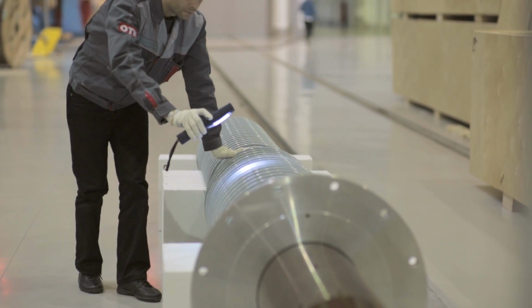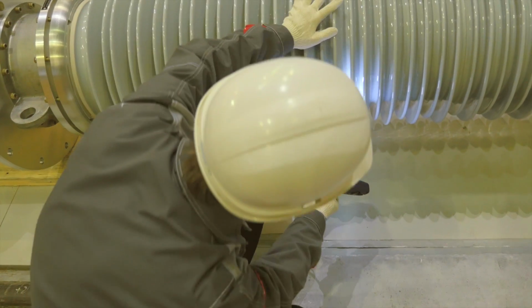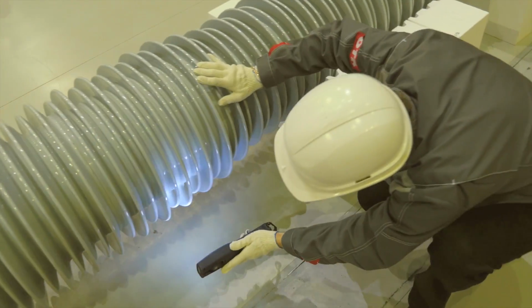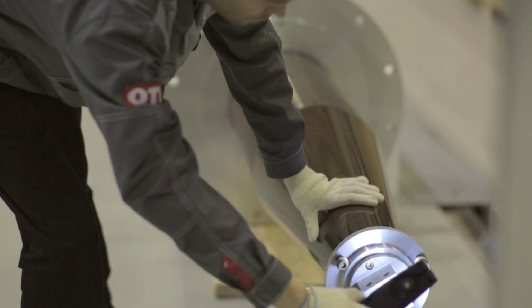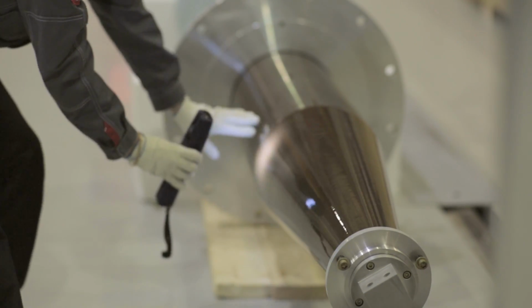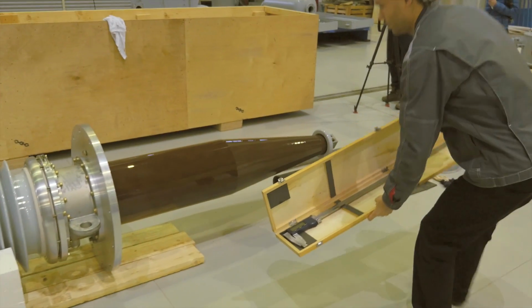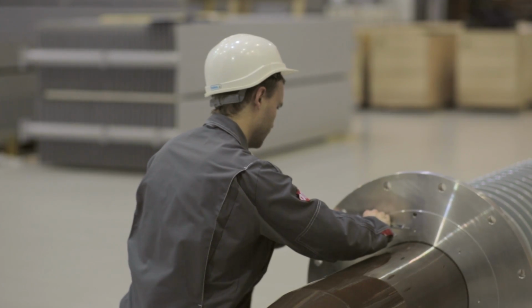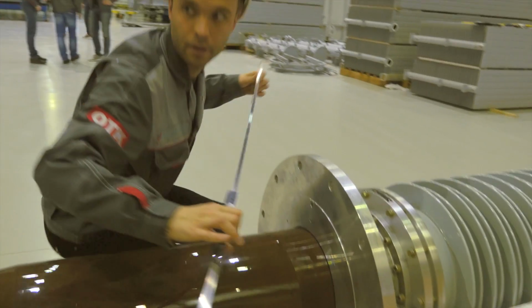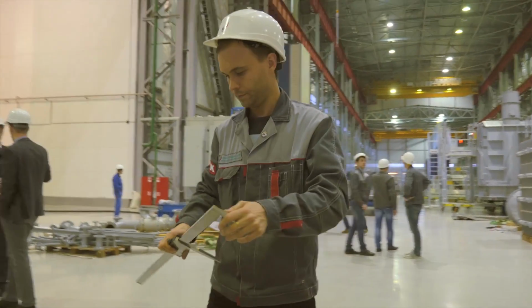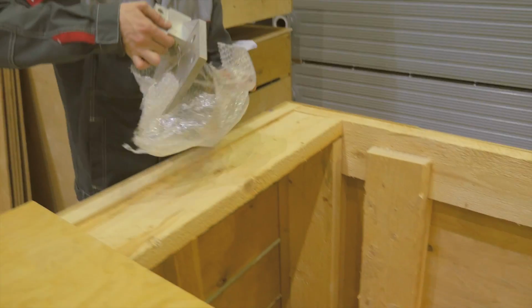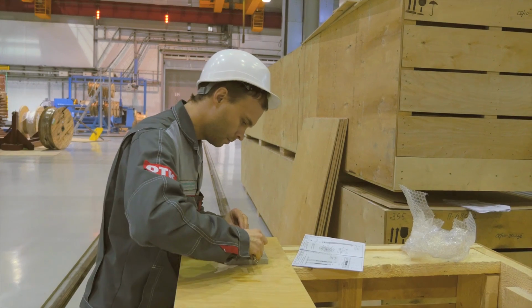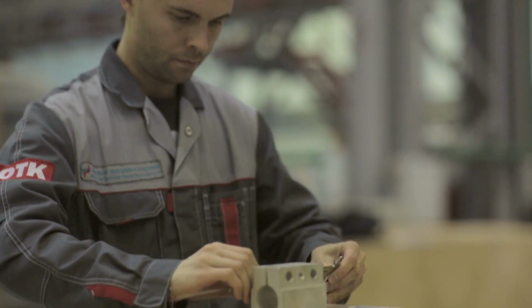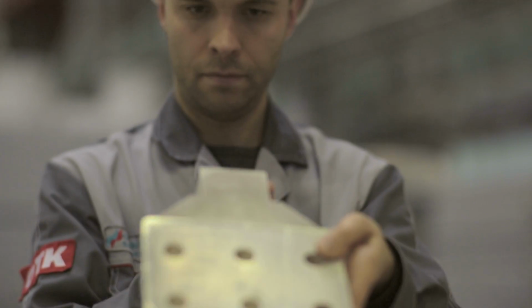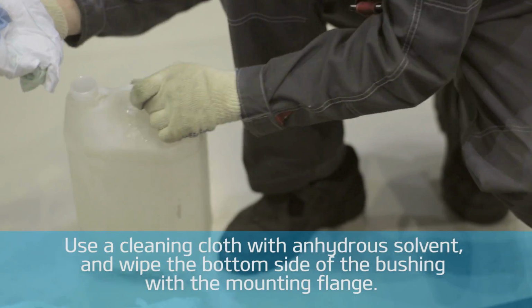There can be a small amount of oil found in the bottom side of the bushing, and especially inside the tube of the draw-lead type bushing, after the tests at the manufacturing plant. This is not an oil leakage indicator. If necessary, take measurements of the bushing unit's geometrical dimensions, though it is an optional procedure. A bushing goes through a multi-stage control in production, and the manufacturer guarantees its conformity with quality management regulations.